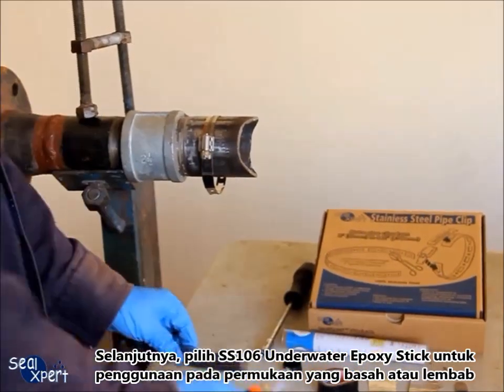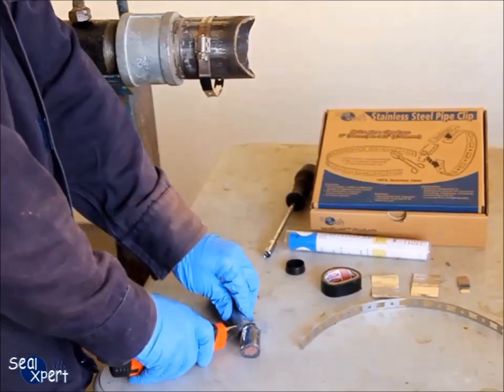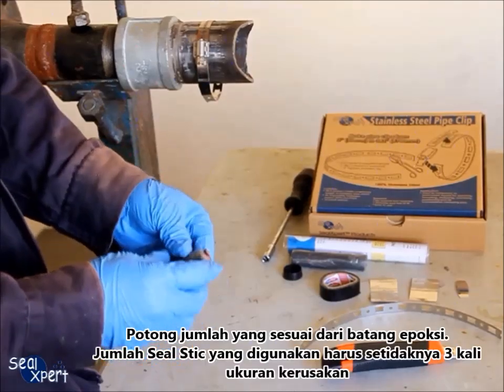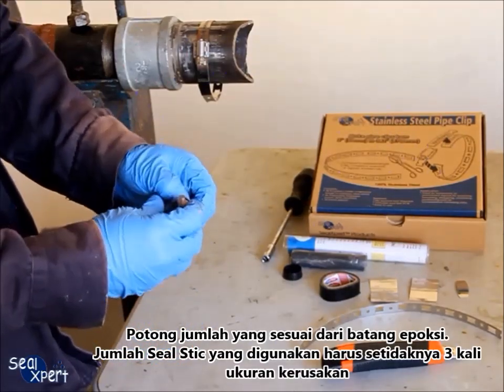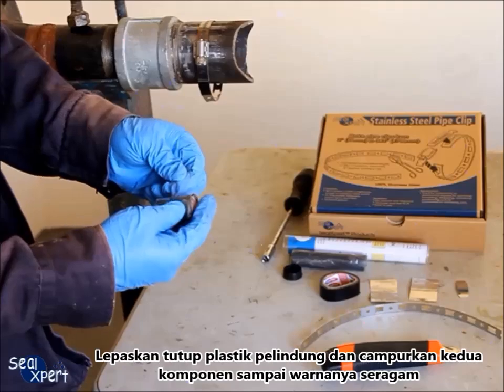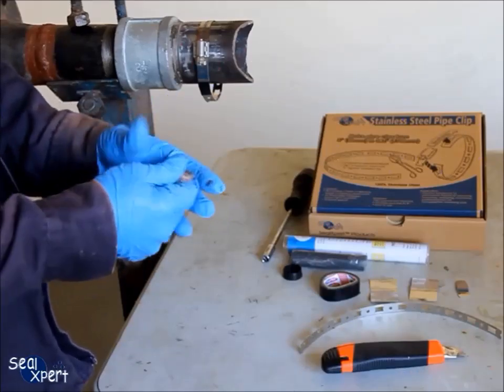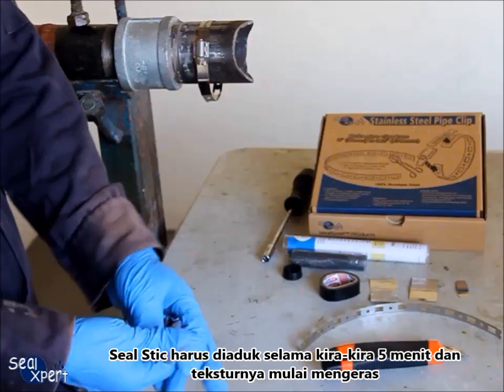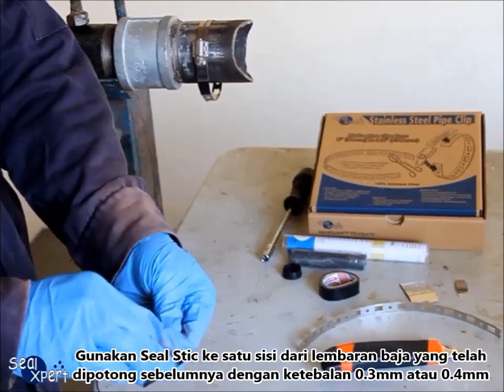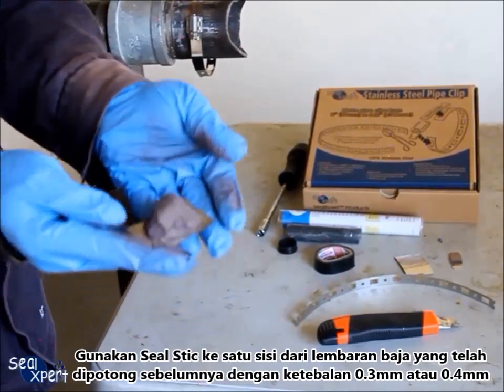Next, select the SS106 underwater epoxy stick for application on wet or moist surfaces. In this video, we are using the SS102 steel epoxy stick. Cut a suitable amount of epoxy stick — the amount used should be at least three times the defect size. Remove the plastic protective cover and mix the two components until the color is uniform. The seal stick should be mixed for approximately five minutes until the texture begins to harden. Apply the seal stick onto one side of the pre-cut stainless steel sheet metal of 0.3mm or 0.4mm thickness.